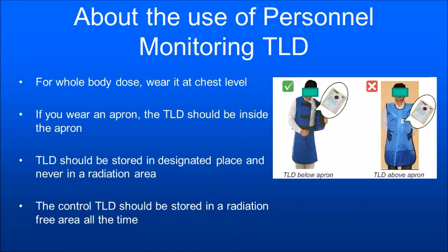You have to be very careful, because I know people who leave it in the control room in a desk, and next day the physicist will come and use the desk for something else, and even he may take it into the room for some purpose, and then the TLDs get exposed. The control TLD should be in a place where there is no radiation. It should be a radiation-free area.